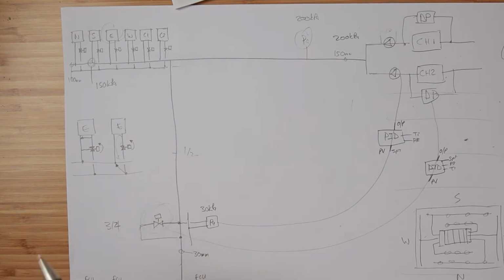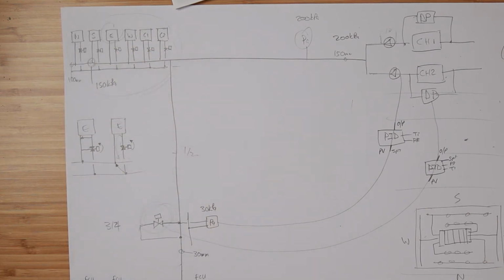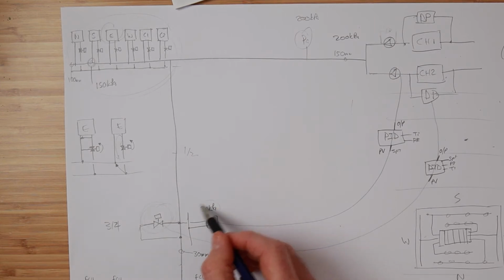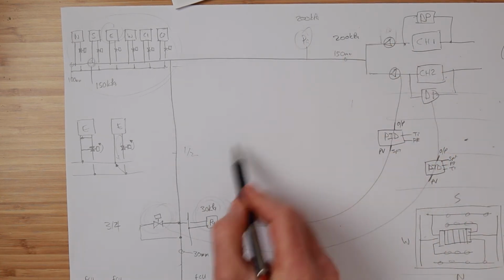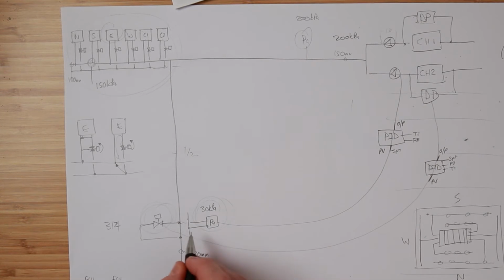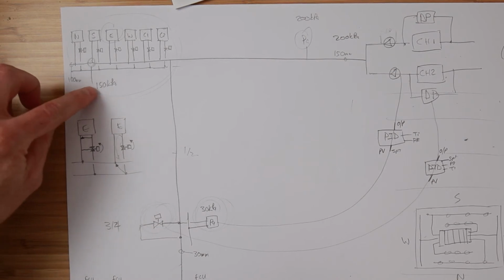So what we should be doing is, when we balance the system, we should be installing our pressure transmitter not 3/4 down the run, but in a location that best represents the load. Here is the load here. This is a good representation of the load for this building. This is not the best representation for the load of this building because we don't have chill water stuff over here. If we had plant rooms all the way down here with AHUs in here, yes, then that would be the best location.